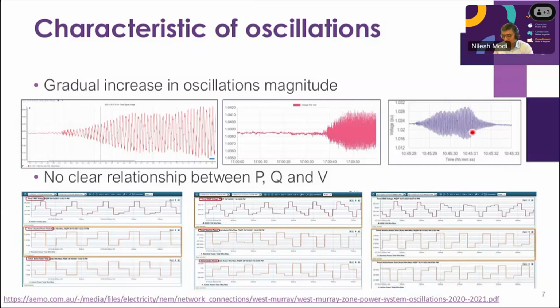We started requesting the data as soon as we found out the oscillations were appearing on the grid. And obviously, we started with any relationship between QV or PV. We requested the data, and then looking at the high resolution measurements, we couldn't establish a clear correlation between QV or PV for any of the IBRs in that part of the network. That was one of the things we found interesting, because normally people would say, okay, look at the QV and look at the PV, and you should be able to find out which IBR is causing that oscillation.